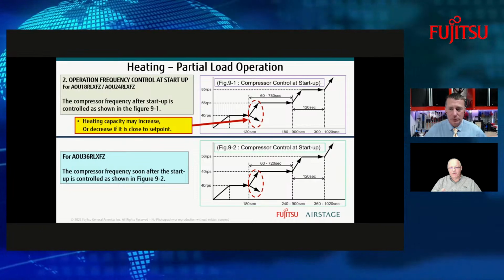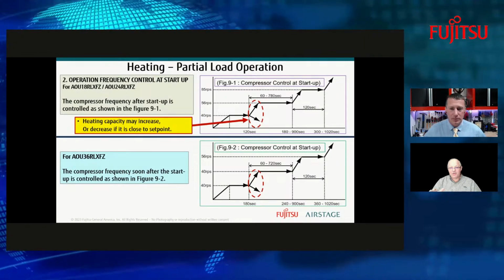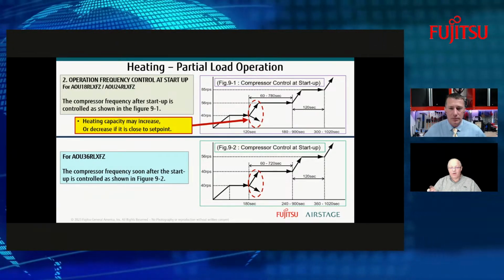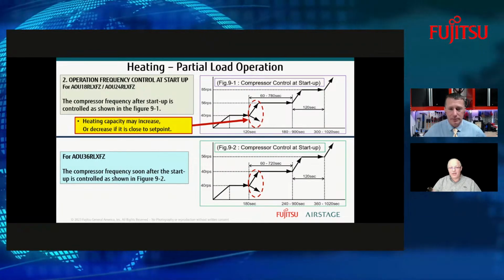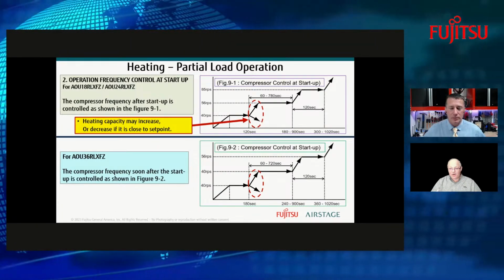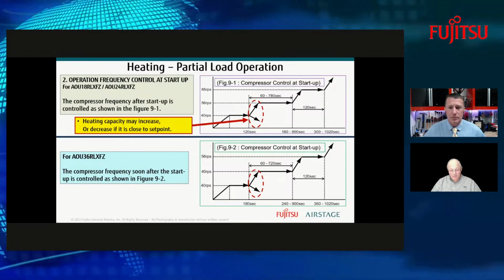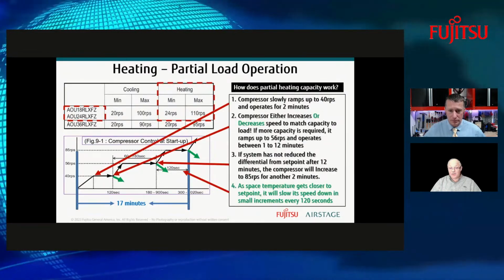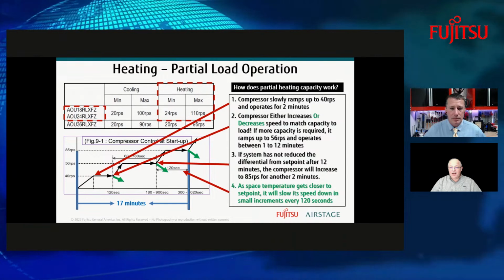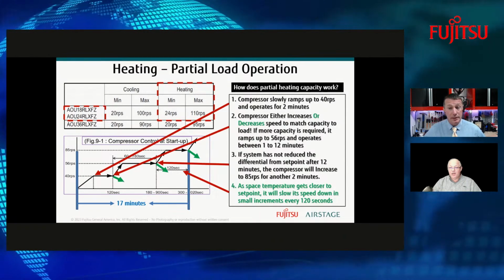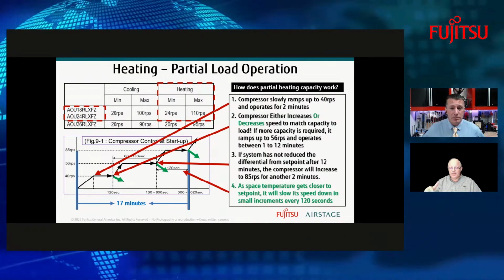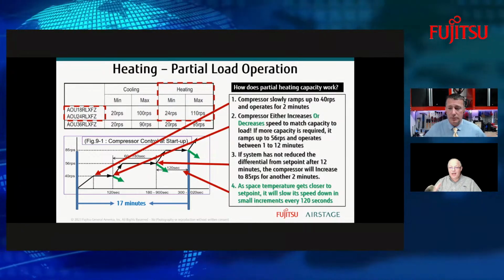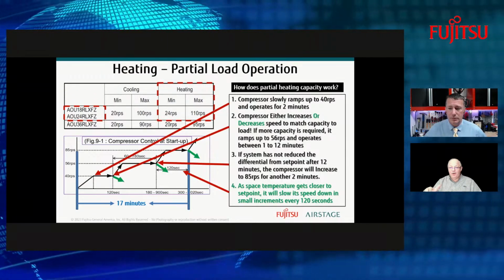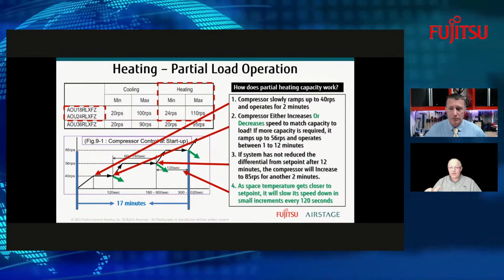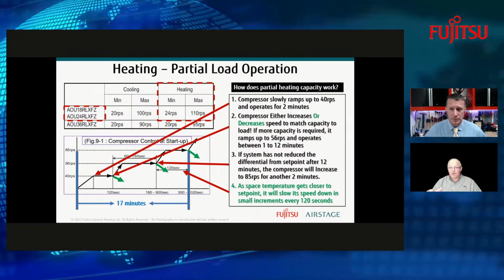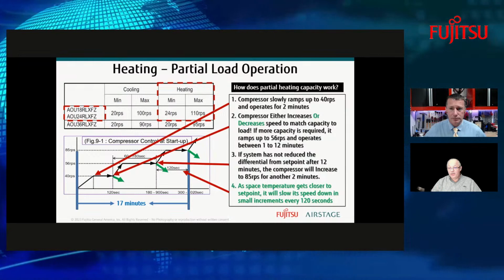That's how these frequencies work. They vary from model to model. The one at the top shows that it has a different range in seconds, different timing than maybe the 3 tons. So depending on the model, it's going to determine when it speeds up and when it slows down. If you want to see how the partial heating capacity works, there are 4 major bullet points that talk about this and how the compressor is going to ramp up from 40 RPS and operate for 2 minutes. The compressor will either increase or decrease depending on whether it needs more capacity.